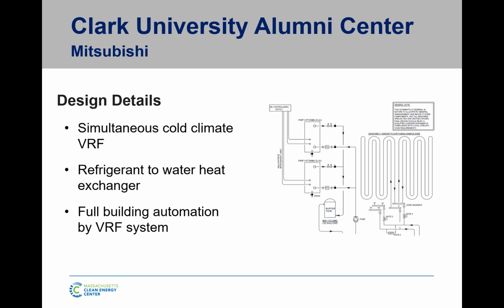So this is using a simultaneous heating and cooling cold climate VRF system. This is a system that's made for these cold temperatures. It utilizes a refrigerant to water heat exchanger. There is a portion of the building where they needed to use radiant floor, mainly due to a large glass exposure in a cafeteria area. So they used a refrigerant to water heat exchanger off of the VRF system to provide hot water for that radiant floor. And the VRF controls completed the task of a full building automation system.